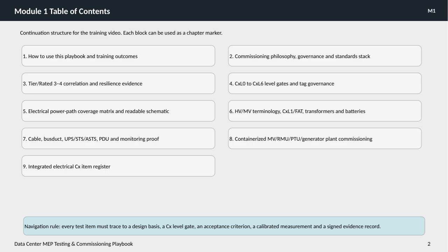for transformers and batteries. The training continues with detailed coverage of cables, bus ducts, UPS systems, static transfer switches, automatic transfer switches, PDUs, and monitoring proofs to ensure reliability. We then look at containerized MV equipment, including RMUs, PTUs, and generator plant commissioning. Finally, we conclude with an integrated electrical commissioning item register, to keep track of all the components involved.